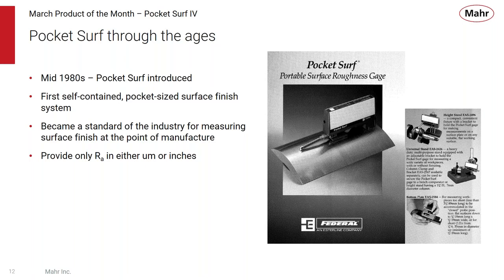It was really the first self-contained pocket-sized surface finish system. There were other devices around at the time, but they were quite fragile, with cables between the drive and the display unit, and you had to be careful with the probing systems because they were so fragile. But the Pocket Surf really packed surface finish measurement into a robust package meant to be used to make surface finish measurements at the point of manufacture. It became, since the 1980s, the standard of the industry for measuring surface finish at the point of manufacture.